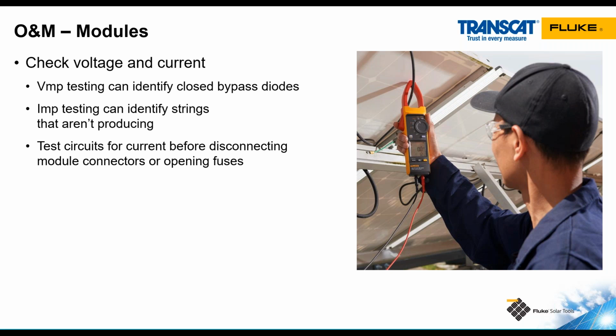So I've shut my system down because I need to do some maintenance on it or some troubleshooting. If I want to open a non-load break rated disconnect, like a fuse holder or a module interconnection, I always want to put a clamp-on meter on that circuit to ensure that there's no current flowing through the circuit before I open up that non-load break rated disconnect. If I open that device when it's under load, it's going to arc. We call that letting the sun out. That arc is going to damage the connector or the terminal that I'm working on, and it's a safety hazard for the technician. Really important to use a clamp meter before you open any of those circuits.